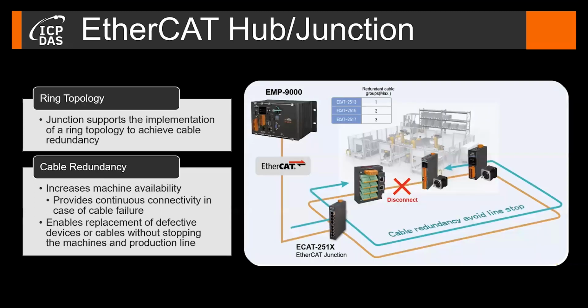The third purpose of the junction is cable redundancy. Cable redundancy can be achieved by implementing a ring topology using a junction module. A ring topology basically enables multipath for the data transmission. In case of a cable or connection failure, the EtherCAT frame automatically selects one of the alternate ring paths to access the slave in the network. Therefore, cable redundancy allows the network to remain available and avoid downtime in case of a single cable failure in the network.